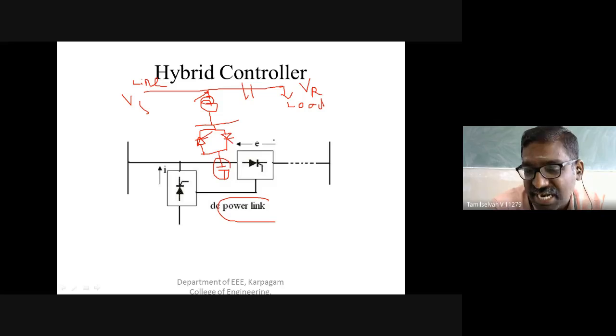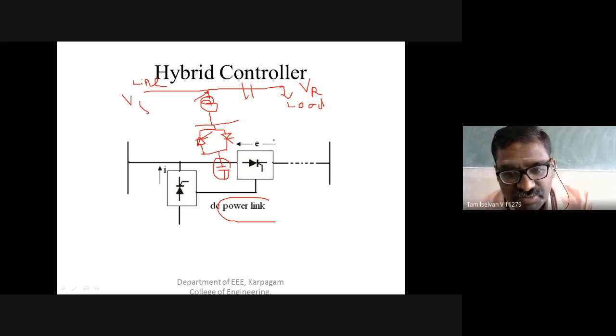Suppose if you are using a StatCom, it means static synchronous compensator. If you are using the StatCom without energy storage or with energy storage, what will happen? What parameters are going to control? It will control the voltage. If you are not using storage devices, it will control only the voltage, VAR compensation, and voltage stability. But if you use the static synchronous compensator with storage, it can also act as automatic generation control and improve the damping oscillation along with voltage control and VAR compensation.